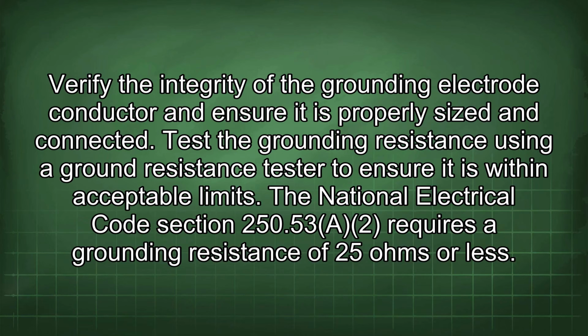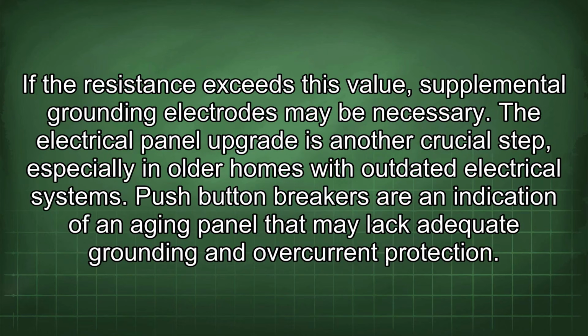Test the grounding resistance using a ground resistance tester to ensure it is within acceptable limits. The National Electrical Code Section 250.53(A)(2) requires a grounding resistance of 25 ohms or less. If the resistance exceeds this value, supplemental grounding electrodes may be necessary.